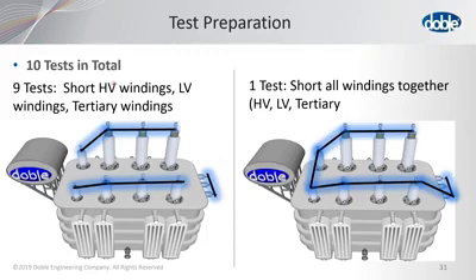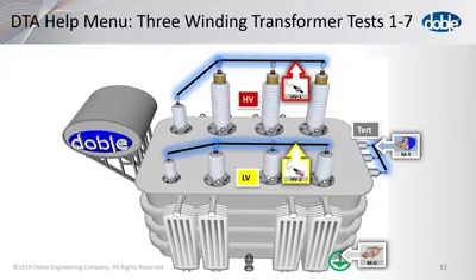For 9 tests, we short the windings as usual, and then for that one test, we short every one of them. That's very similar to the M4100. But what makes it a little different is we have two high voltage leads with the M7100. We have an HV1 and an HV2. Both these leads can apply voltage as a source, or be grounded, or be guarded, or be measured. So it's got 4 different functions for each one of the high voltage leads.